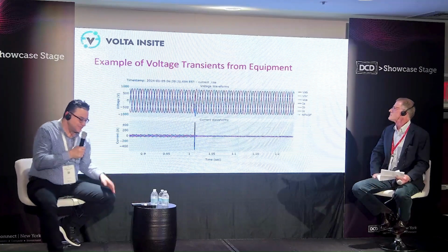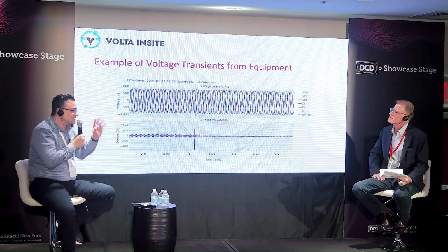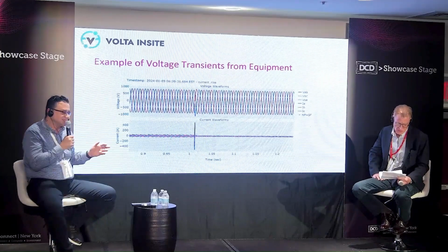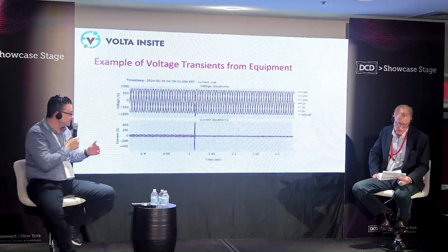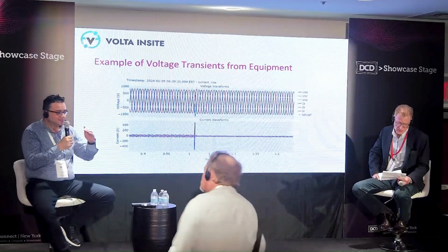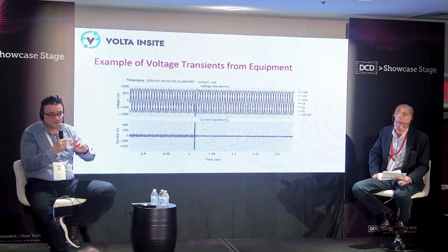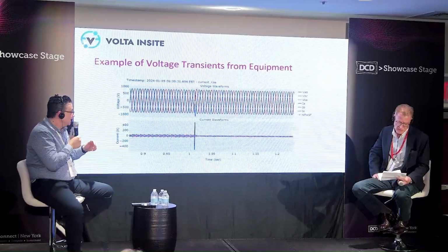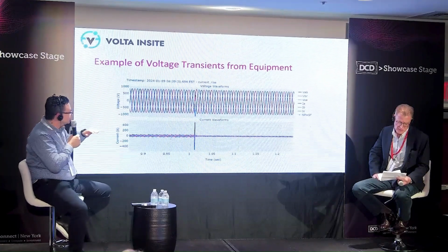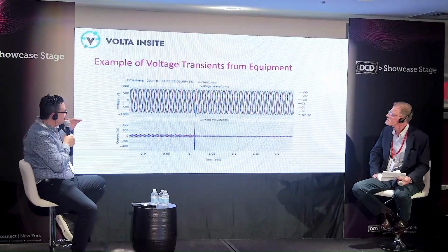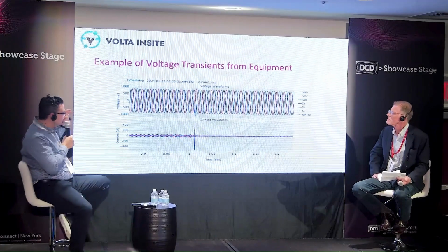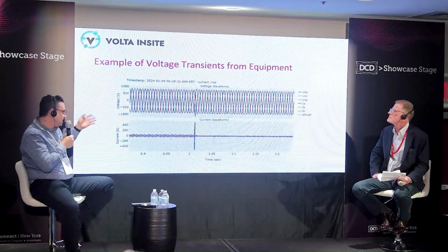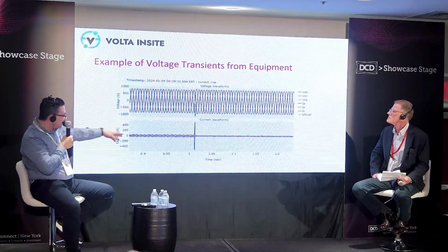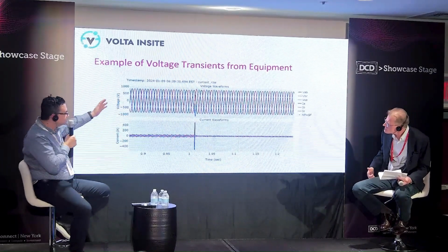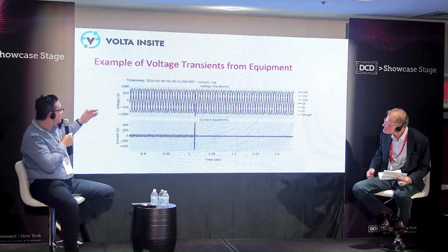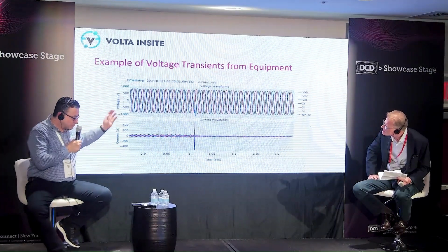There's always ghost electrical problems within any facility, whether it's a data center or a manufacturing facility, and that leads to different pieces of equipment coming online potentially or malfunctioning. So if we're running this continuous waveform capture, the beauty is we can see everything. This is a piece of equipment that was malfunctioning in the field, and you'll notice a massive current spike with a lot of voltage variation being created on your power source.